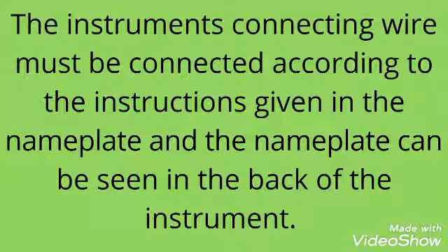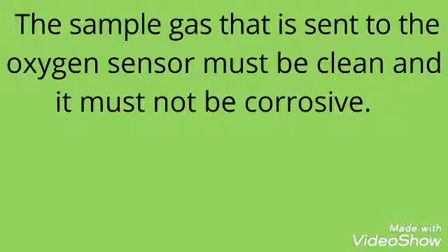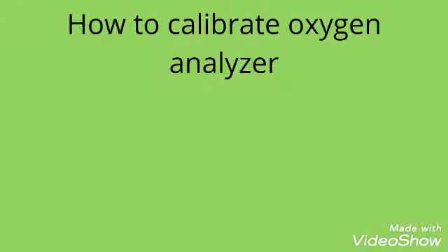The instrument connecting wire must be according to the standard and according to the instruction on the nameplate which is at the back of the instrument. The sample gas that is sent to the oxygen sensor must be clean, must be dry, and must not be corrosive. So we should clean the sample before measurement.